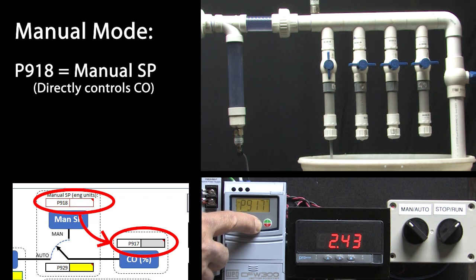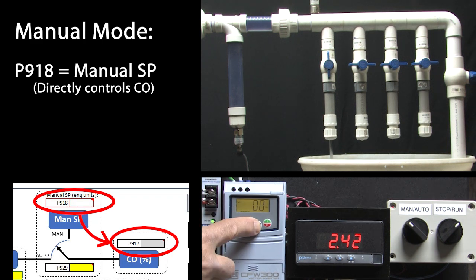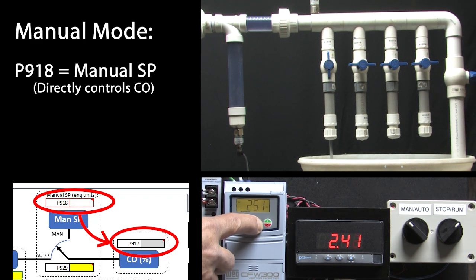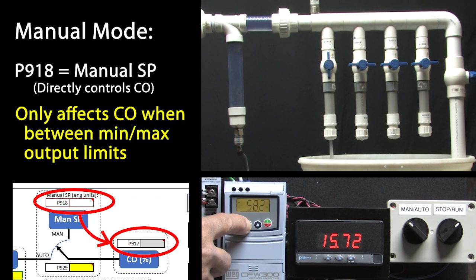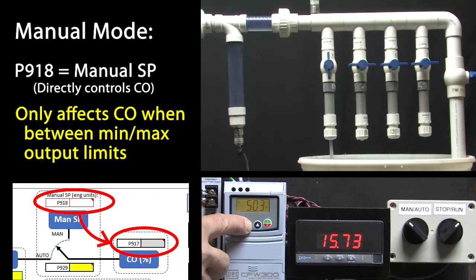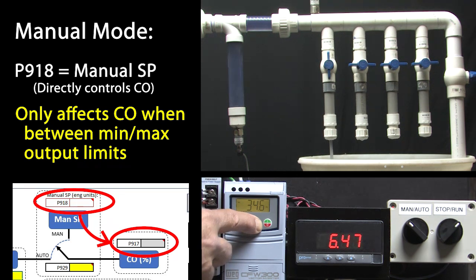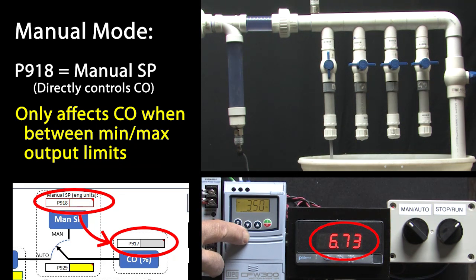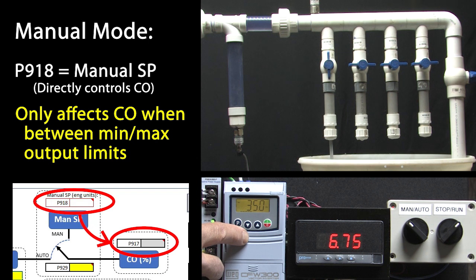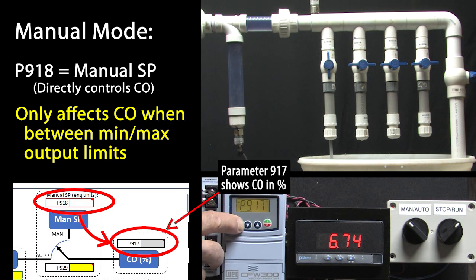Remember, we set the min and max motor speed to 25 to 50 Hz. So while we can set the manual set point to whatever we want, it won't actually do anything until it's between those two frequencies. If I go to 35 Hz, sure enough the pressure is near 7 psi, exactly what we expect to see from the plot we created in the previous video.